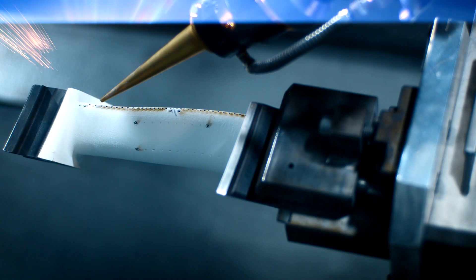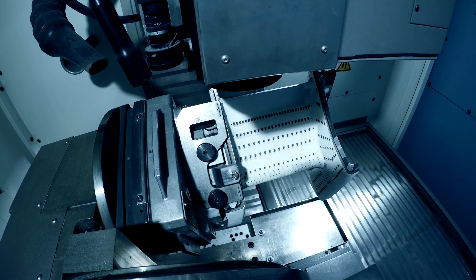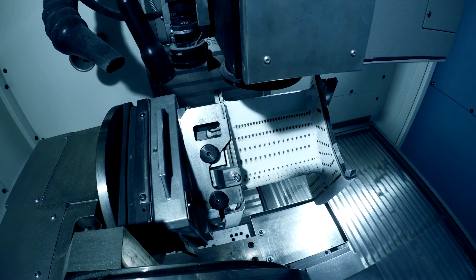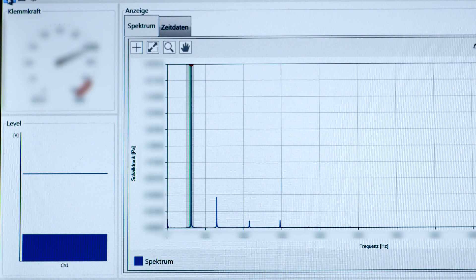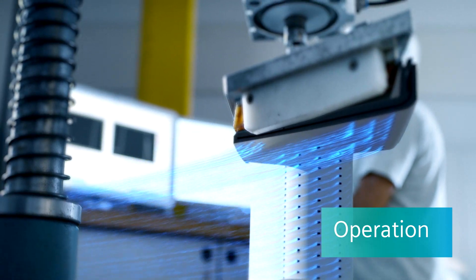Cooling holes are reopened and reshaped by means of laser technology in accordance with the original design parameters. The frequency and the cooling airflow measurements are verified for reliable operation.